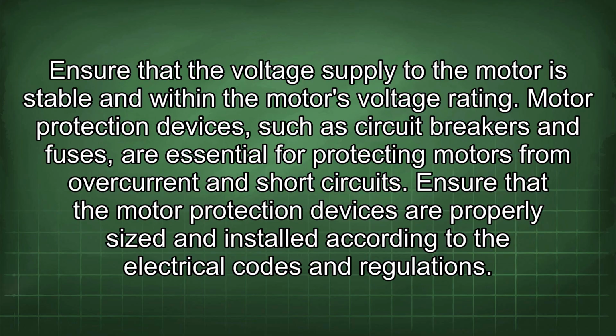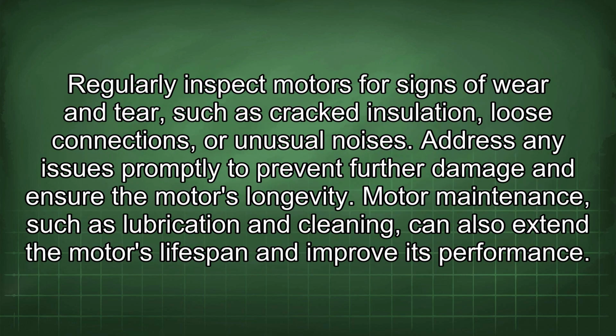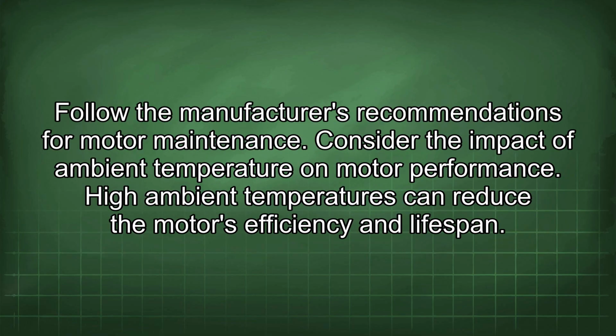Motor protection devices, such as circuit breakers and fuses, are essential for protecting motors from overcurrent and short circuits. Ensure that the motor protection devices are properly sized and installed according to the electrical codes and regulations. Regularly inspect motors for signs of wear and tear, such as cracked insulation, loose connections, or unusual noises. Address any issues promptly to prevent further damage and ensure the motor's longevity. Motor maintenance, such as lubrication and cleaning, can also extend the motor's lifespan and improve its performance. Follow the manufacturer's recommendations for motor maintenance.